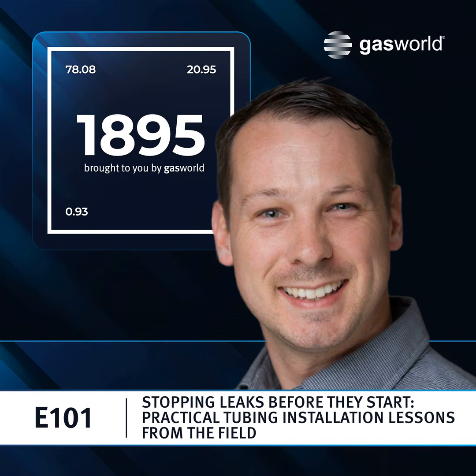I think you also asked about diagnostics. From a diagnostics perspective, obviously the best diagnostic is to use visual inspection. We've got some tools around that space to help with visual inspection, things like gap gauges, Snoop, which is kind of a leak detector and fluid, that if you've got a pressurized system, you'll be able to see bubbles and things like that. But a lot of that doesn't happen until you actually can start running the system.